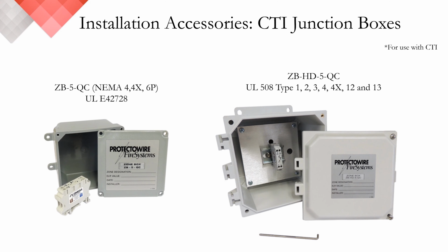And here we see the junction boxes specific to our CTI detector. The only difference between these and what we saw in the previous slide is that terminal block that you see in front of the screen. That terminal block is specific to CTI detectors only, providing us the continuation of that thermocouple principle throughout the run.